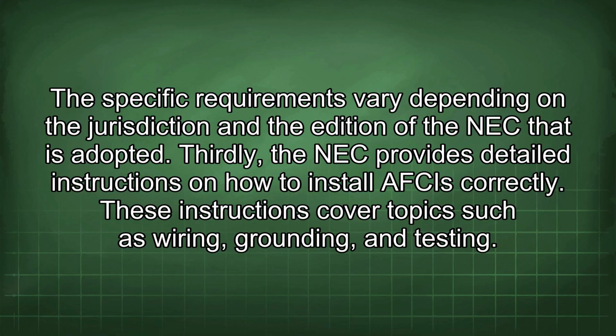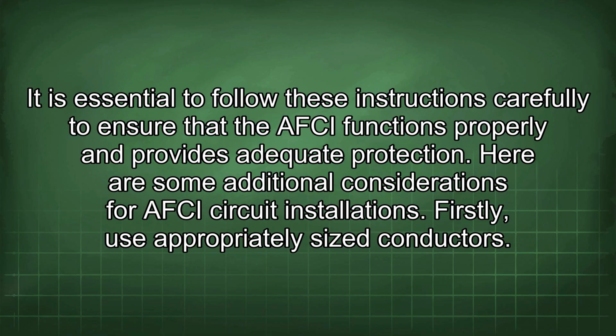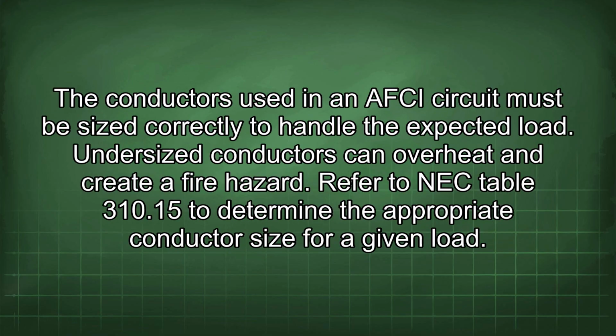Thirdly, the NEC provides detailed instructions on how to install AFCIs correctly. These instructions cover topics such as wiring, grounding, and testing. It is essential to follow these instructions carefully to ensure that the AFCI functions properly and provides adequate protection. Here are some additional considerations for AFCI circuit installations. Firstly, use appropriately sized conductors. The conductors used in an AFCI circuit must be sized correctly to handle the expected load. Undersized conductors can overheat and create a fire hazard. Refer to NEC Table 310.15 to determine the appropriate conductor size for a given load.